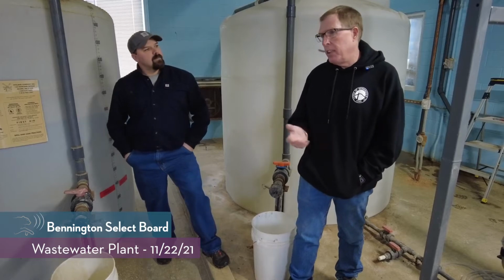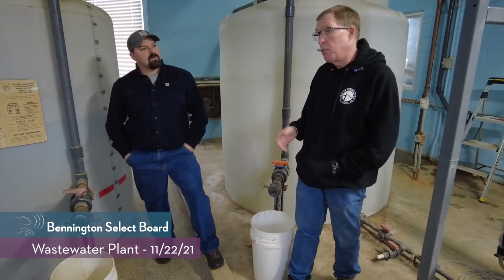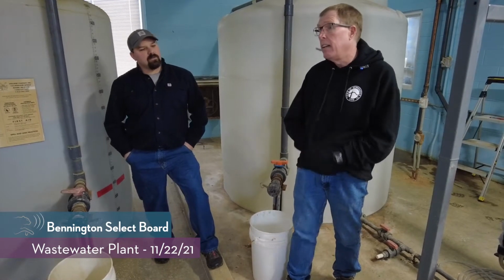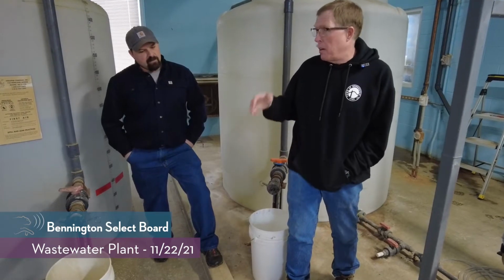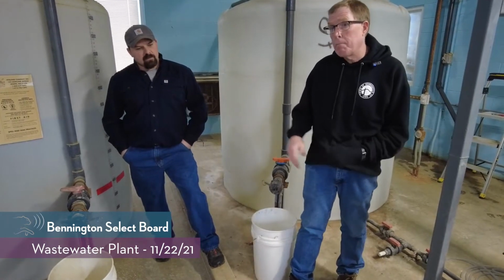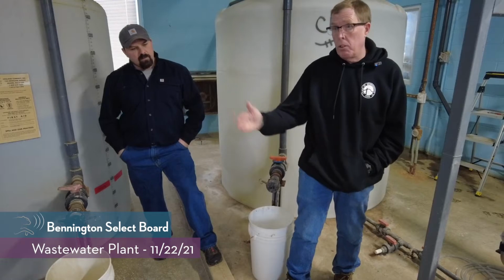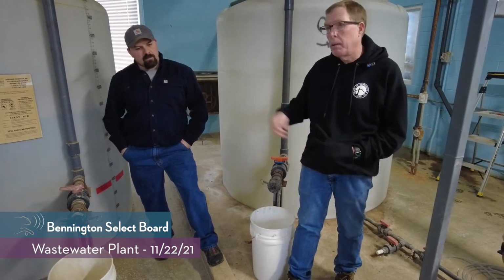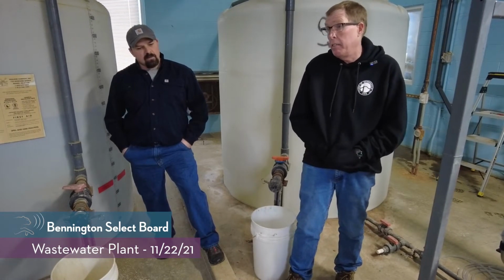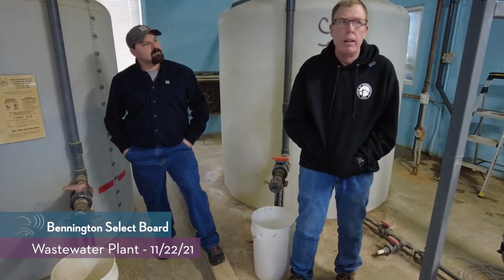We can run 50 to 60 gallons of hypo a day, and typically about half as much bisulfite. The chlorine gets used up as it goes through the chambers, so we'll run probably about 25 to 26 gallons a day of sodium bisulfite to dechlor it.